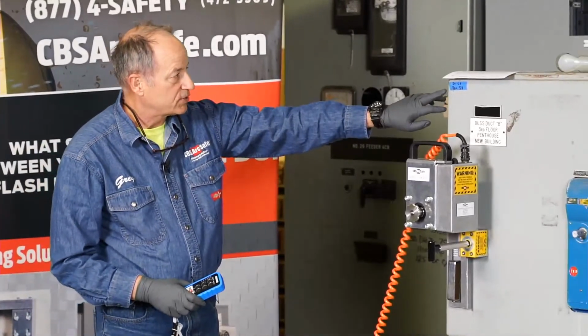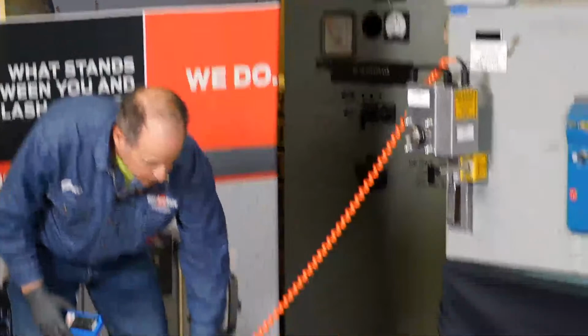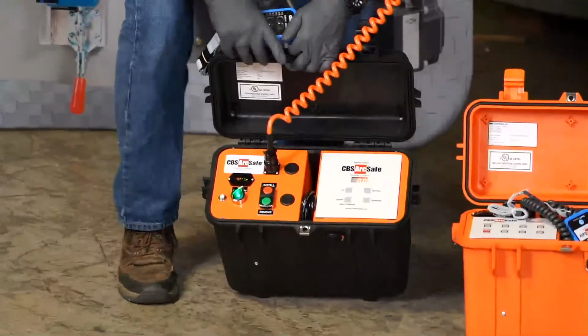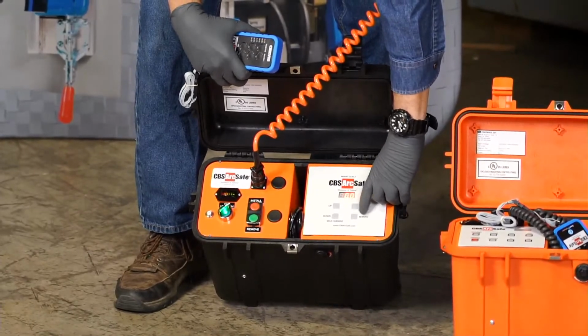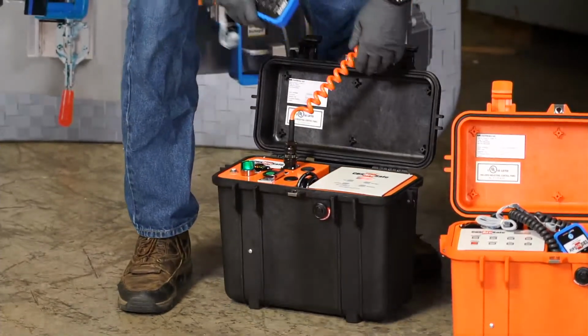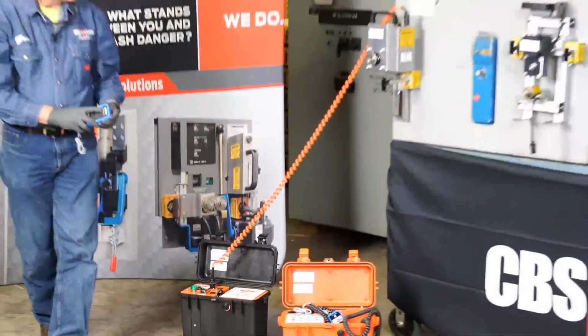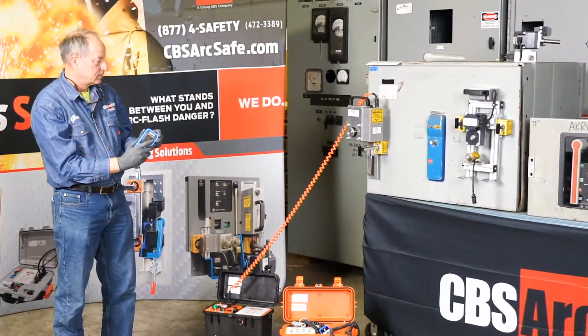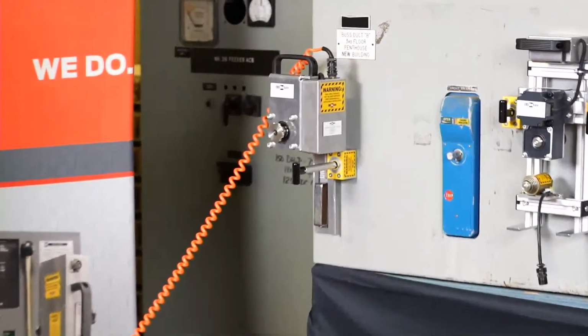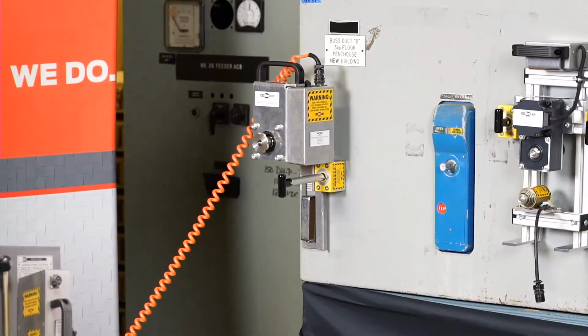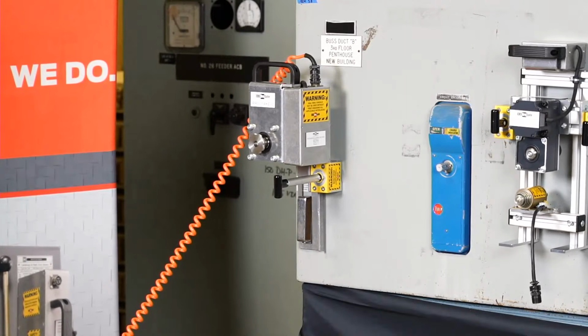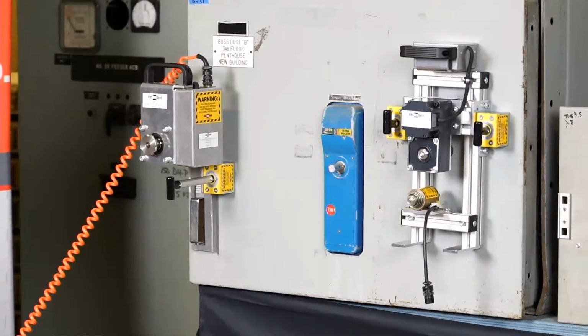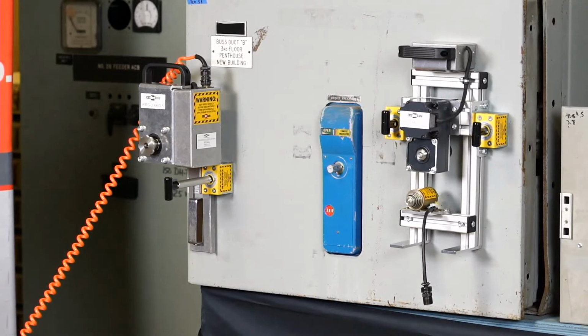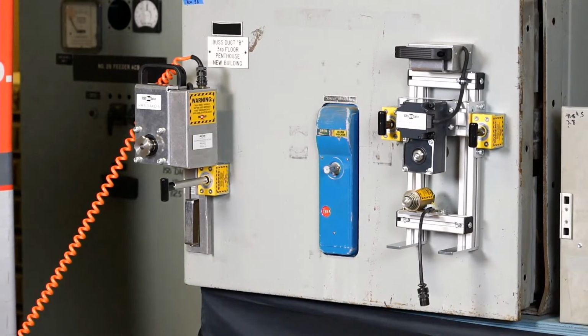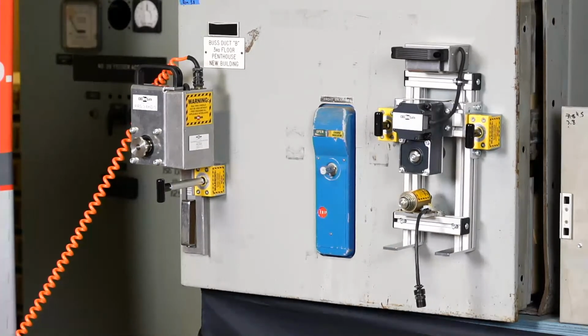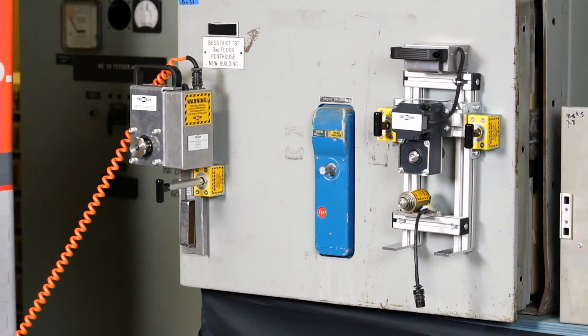So we'll just check our settings here of 6.6 and 3.8. And what we'll do is we'll look at install, 6.6 and 3.8. And all I need to do now is I simply touch the remove button, and the breaker is going to rack out. And again, you want to be outside the arc flash hazard boundary when you do this. Standing right here doesn't get you any safety. And now the breaker's racked out.